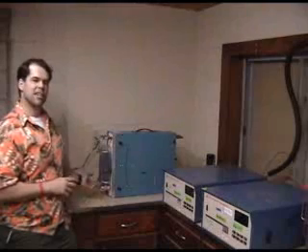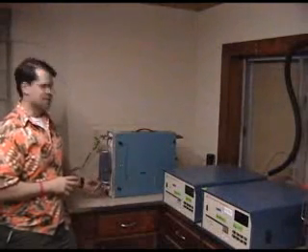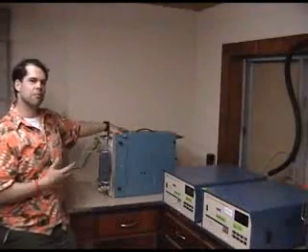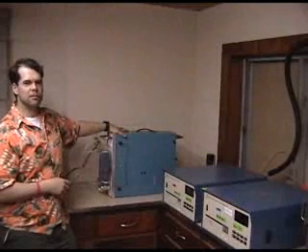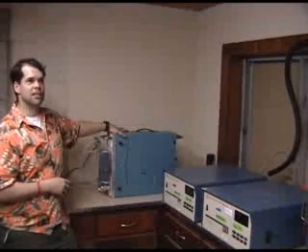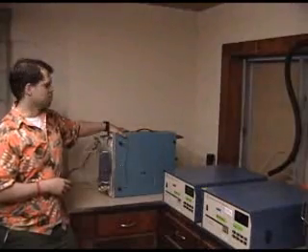We need to test to make sure that you made all the connections back properly and that there's no leaks in the caps or the lines. How do we do that? We got a little red button in the back of the zero air tank that pressurizes these canisters for you, so you can listen for leaks. Or if you're really wanting to check leaks, you can use some Snoop or soapy water.